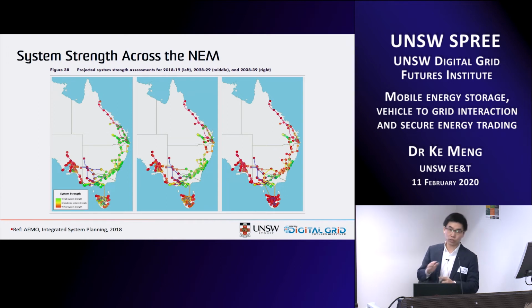So why is system strength so important? As I mentioned, compared with a stronger grid, a weaker grid might show more issues, like voltage issues — voltage may dip deeper and require much longer time to recover. When renewable generators are connected to a weaker grid, we see more issues, because one of the key advantages of renewable generators is that they're power electronics interface devices, able to respond very quickly to any disturbance in the grid. But sometimes this fast response capability translates into undamped voltage oscillations.